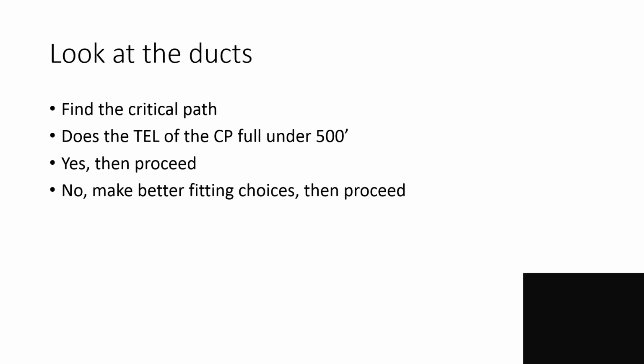Let's look at the duct system itself. If you're familiar with Manual D, you'll know that the critical path is the one duct run that has the longest total effective length. So we want to do a calculation from our longest return to our longest supply and make sure that it has a TEL under 500 feet. And if it doesn't, well, then use some better fittings or do something so it does. As long as the duct system stays under that prescribed velocity and doesn't have a total effective length greater than 500 feet, which is not out of the question, but for the most part, I'm used to measuring effective lengths between 300 and 400, then we've determined that we have a duct system that will support the airflow that is required. And if we end up with velocities that are lower, that's fine. Lower velocities will never hurt you.